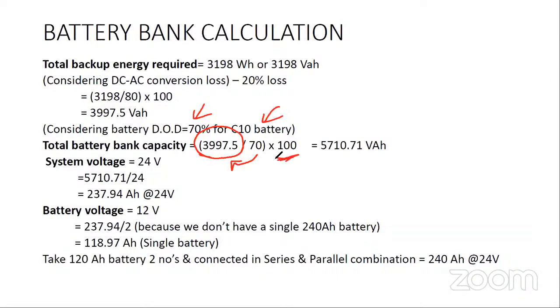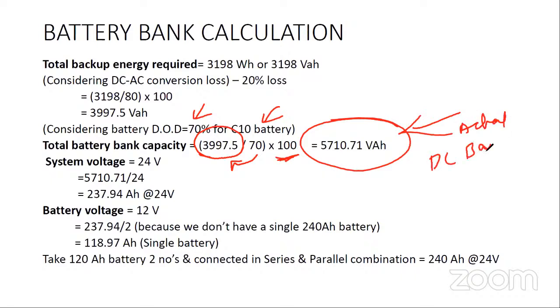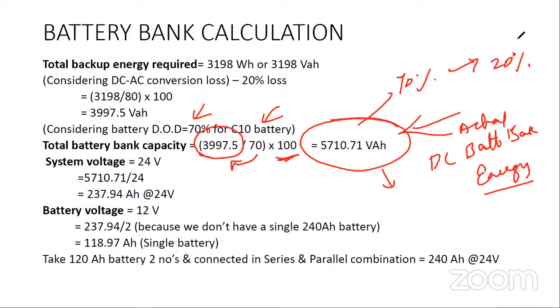Then I need to arrive at my 100% capacity, so I'm dividing by 70 into 100. I'm getting 5710 volt ampere hour. This is my actual DC battery bank energy. If I have this much energy inside my battery bank, I'm going to use 70% of it, and I'm going to lose 20% during conversion. Then finally I will get this much energy. If you calculate only for this, you will not get this.